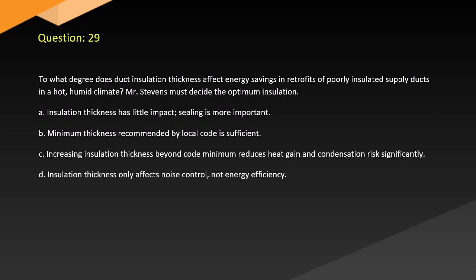Question 29. To what degree does duct insulation thickness affect energy savings in retrofits of poorly insulated supply ducts in a hot, humid climate? Mr. Stevens must decide the optimum insulation. A. Insulation thickness has little impact. Sealing is more important. B. Minimum thickness recommended by local code is sufficient. C. Increasing insulation thickness beyond code minimum reduces heat gain and condensation risk significantly. D. Insulation thickness only affects noise control, not energy efficiency.